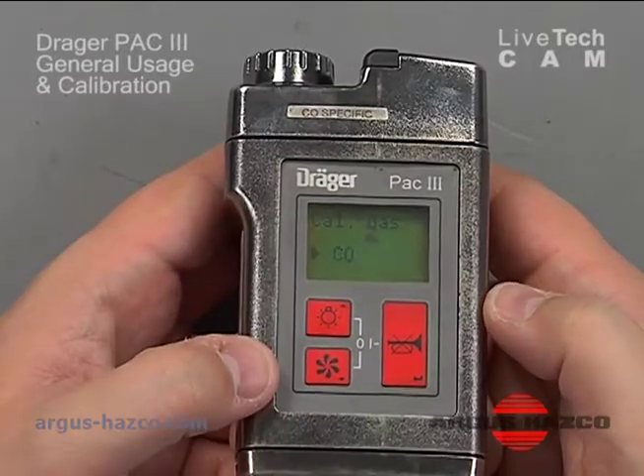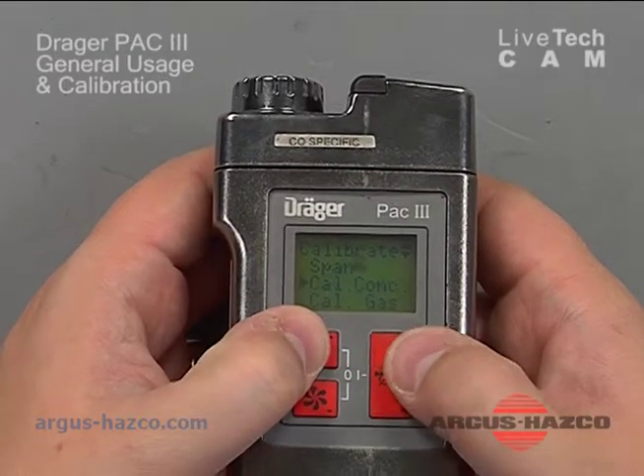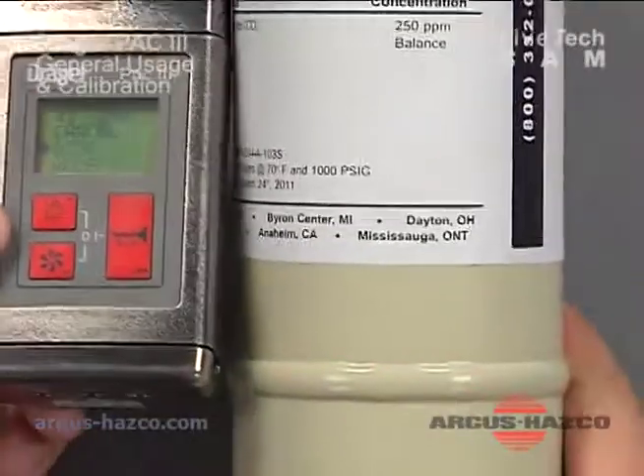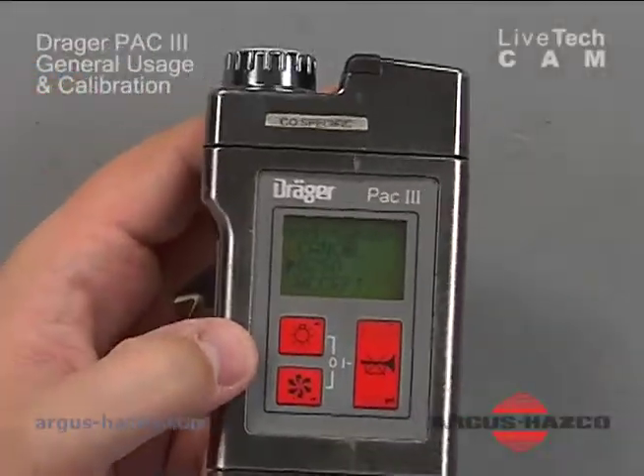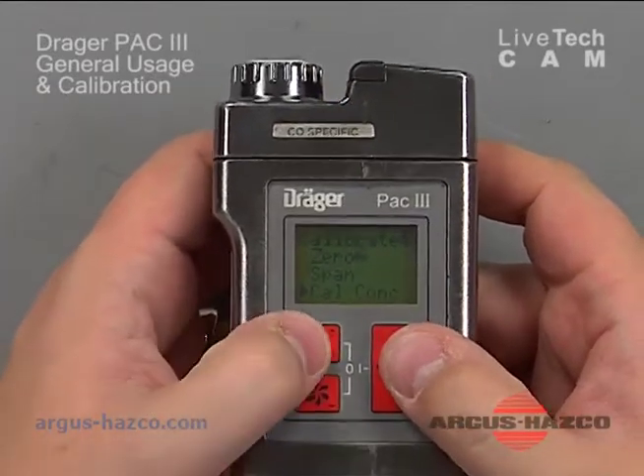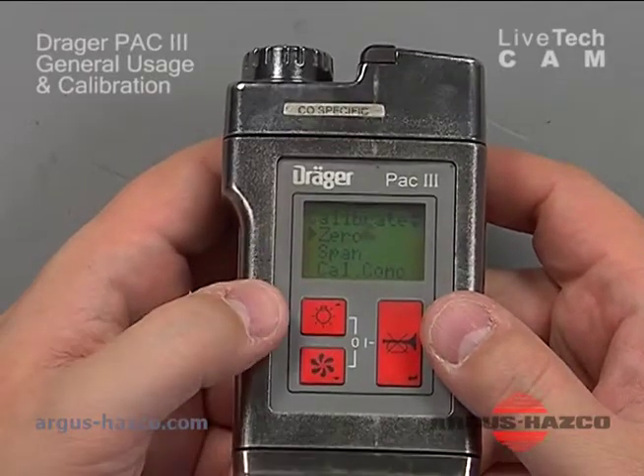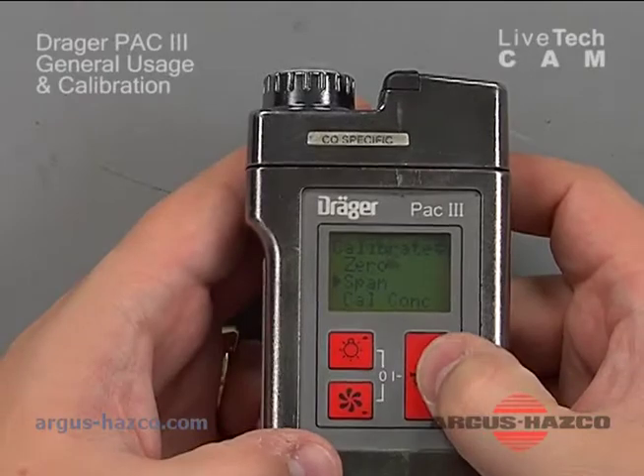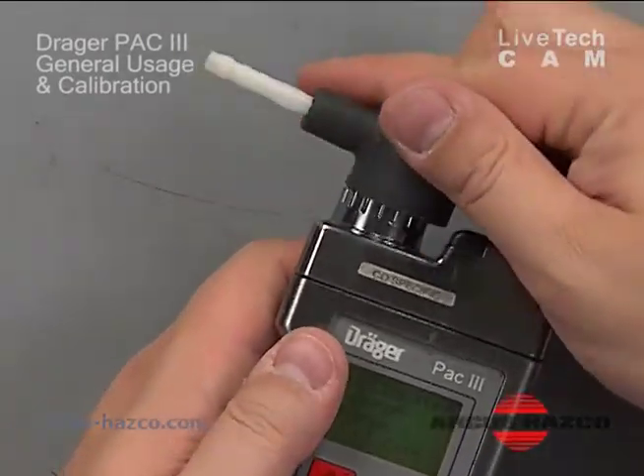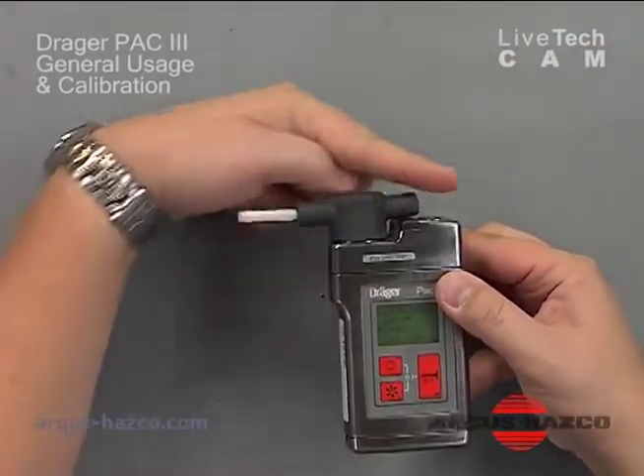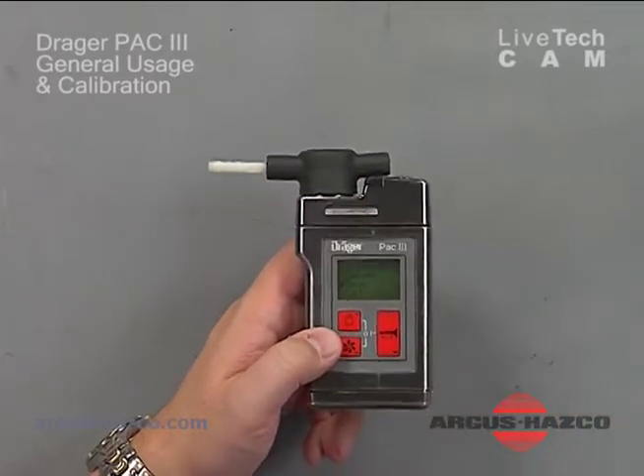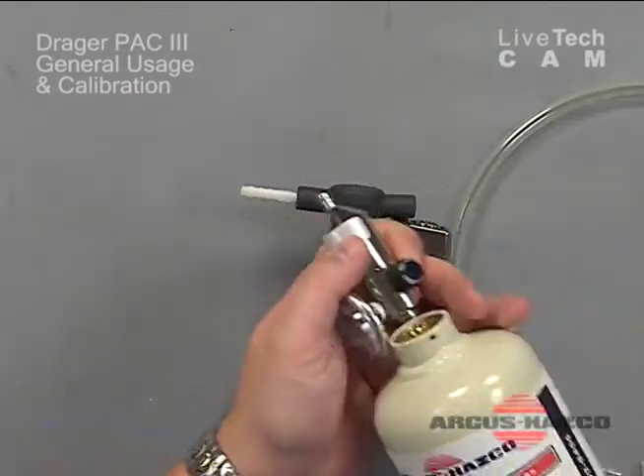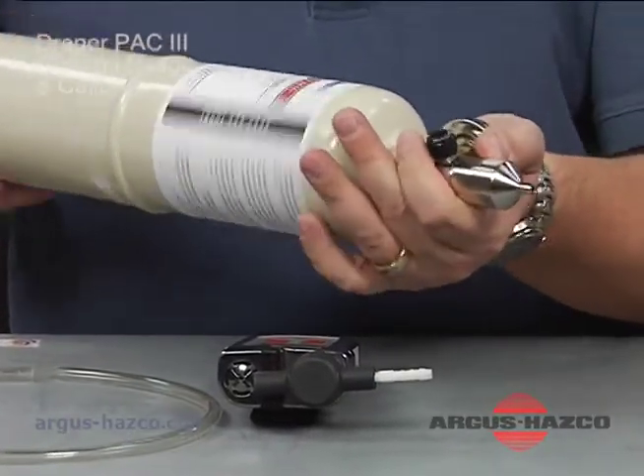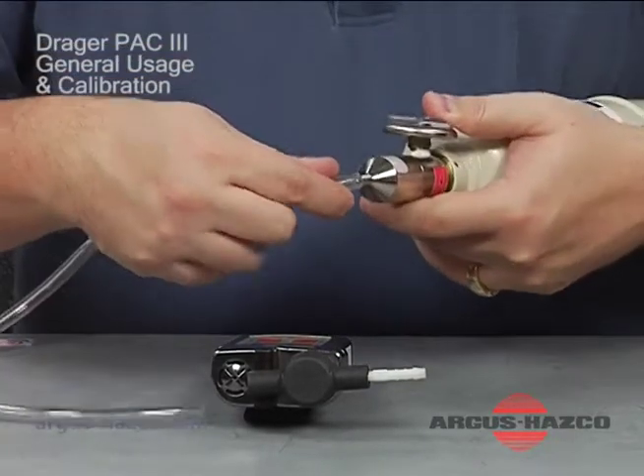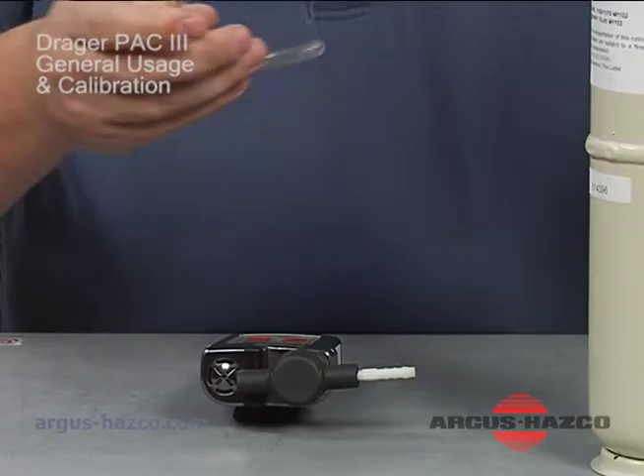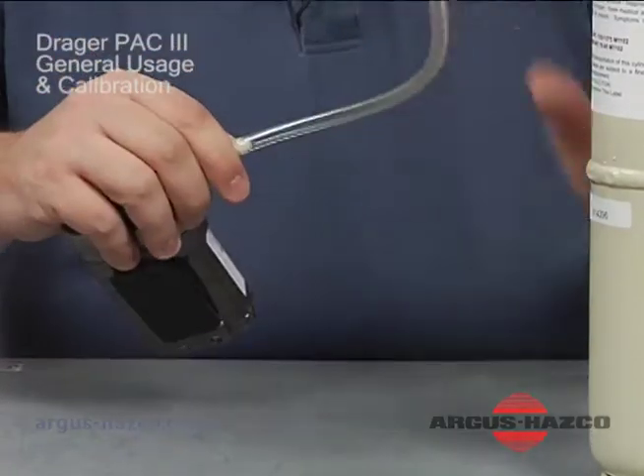The cal gas you want to set up is carbon monoxide. That's what we're using. The cal concentration is 250, which you can tell on the cylinder is 250. So you can accept that. We've already done the zero, so at this point you could do a zero fresh air calibration, but we've already done that by pressing the hotkey. The span calibration, you want to attach your cal adapter. So the gas will flow through. And then you have your tubing, and you want to attach your regulator to your cylinder. Attach the tubing to the regulator. Attach it to your calibration adapter.